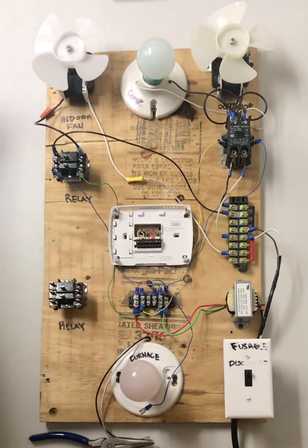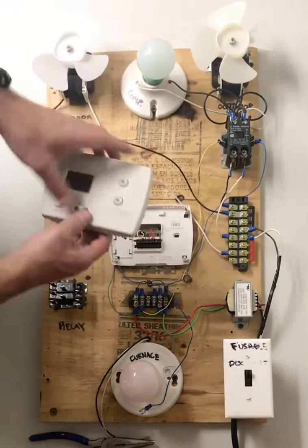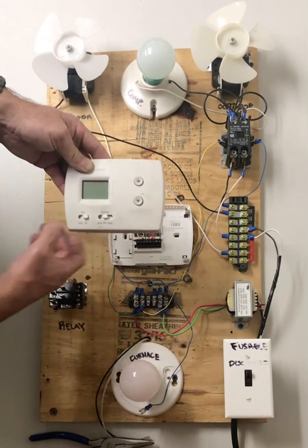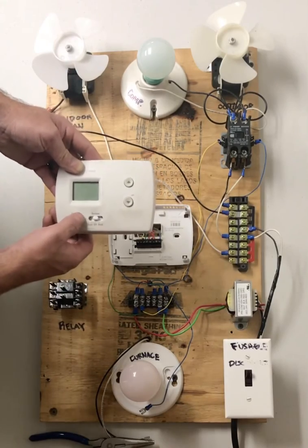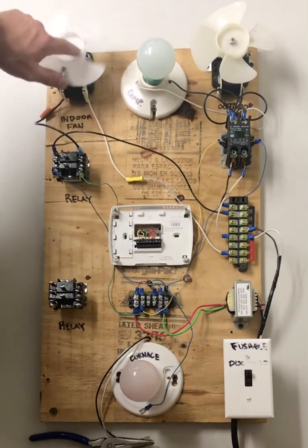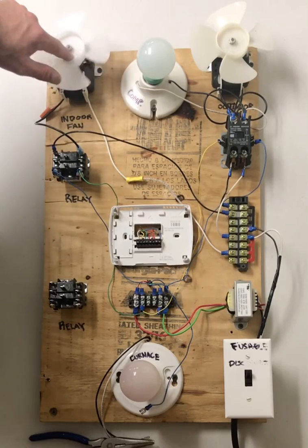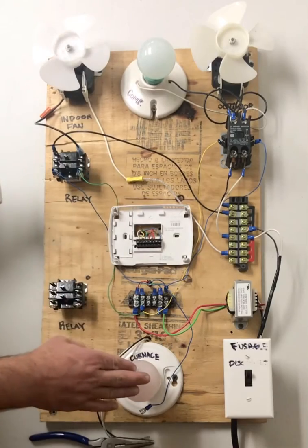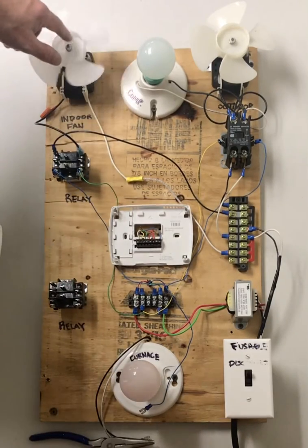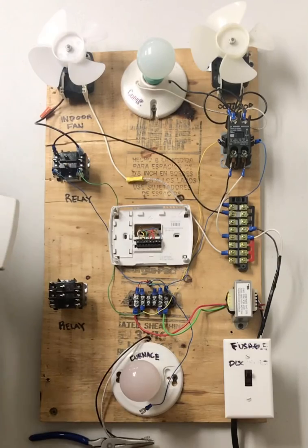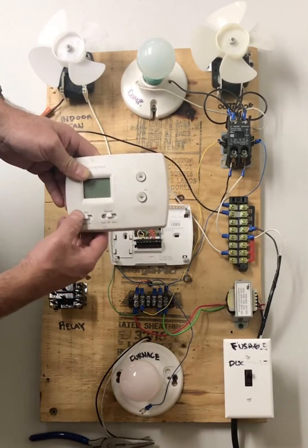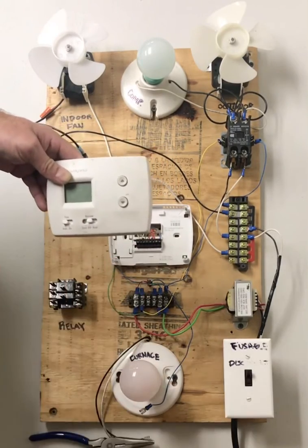G is your indoor fan motor. So if you've got your thermostat plate here and you switch your fan from auto to on, like that, that energizes the G terminal, which energizes only your indoor fan. So instead of the indoor fan coming on with a cooling call or a heating call, the fan comes on all by itself, regardless of what you're calling for, or if you are calling for anything. You could be calling for nothing. You could have the switch set to off and still turn your fan on and circulate air through your space.